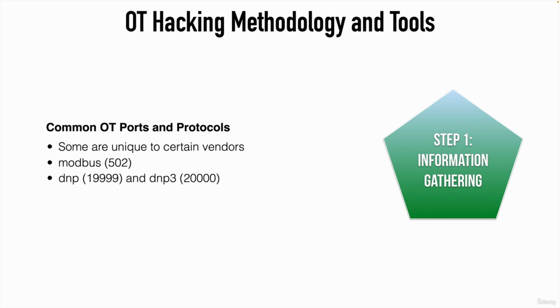We also have DNP over port 19999 and DNP3 over port 20000 - DNP meaning Distributed Network Protocol. We see these primarily in utilities industries and places like oil and gas as well. We have Fieldbus over port range 1089 through 1091, used to aggregate communication between multiple sensors or switches and PLC devices - think of it almost like an Ethernet switch, distributing connections without needing direct mesh connections between every device.